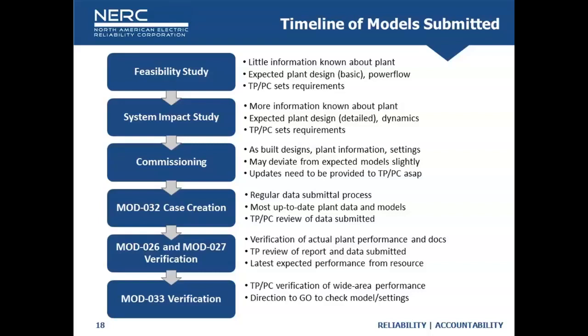We have seen very successful implementations of that, with transmission planners and planning coordinators having very good feedback with the generator owners to understand what the model is representing and what it's not representing. And we have horror stories of the transmission planner essentially signing off on anything, with test reports that say no model is provided, for false reasons. So we have the full spectrum of good and bad. We need to come to the middle and have a good understanding of what the expectation is there. When you get a test report, you should be reviewing it.